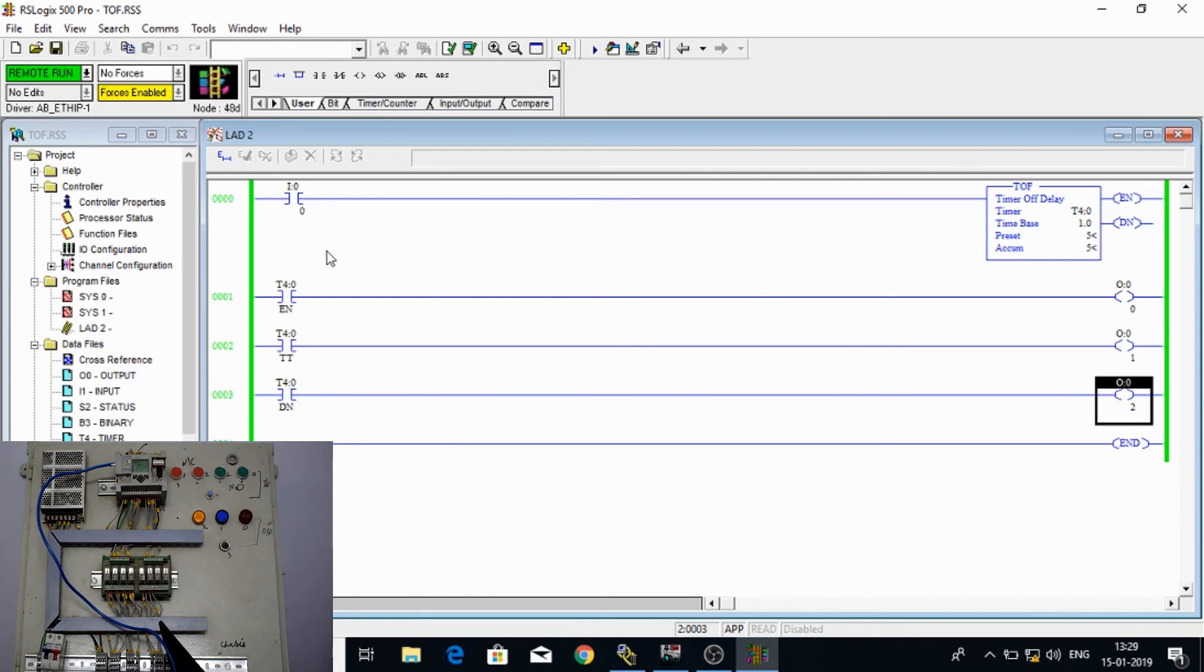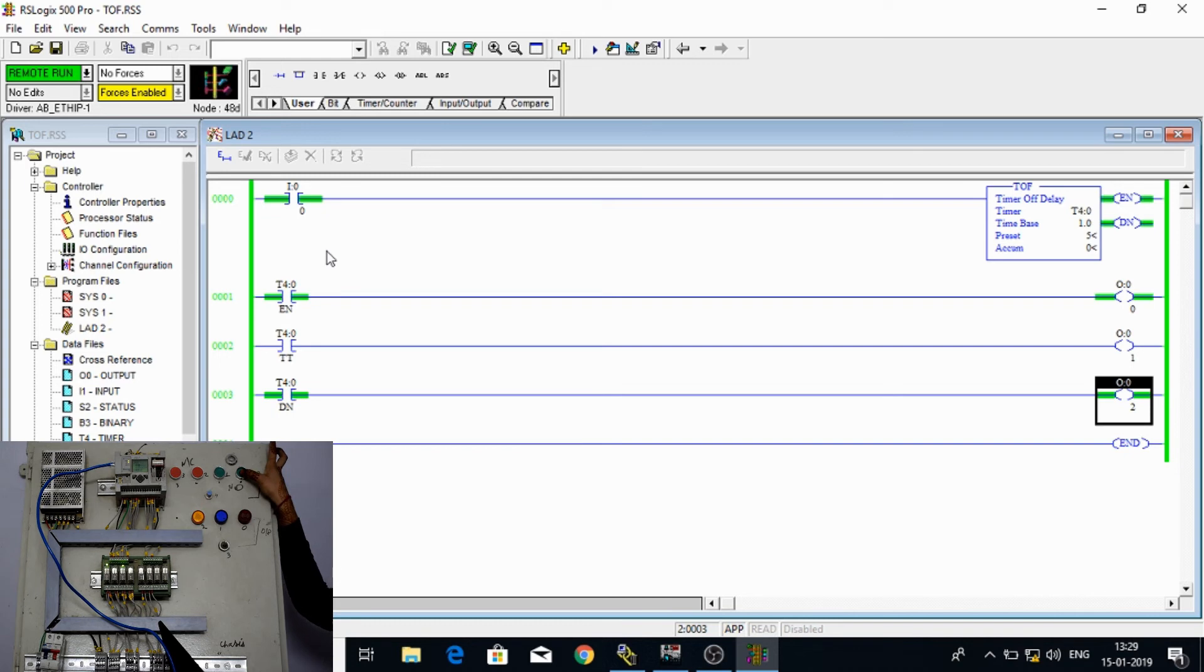Now we have studied that TOF gets starts when our rung becomes false from true. So here we can see our rung is false now and when I press our input 0 we can see timer is not getting start as that was case in TON. Here my condition will get fulfilled when my rung becomes false. And as I remove my input, as my rung becomes false we can see our timer is getting start and after 5 seconds our output gets off as we can see in panel also.